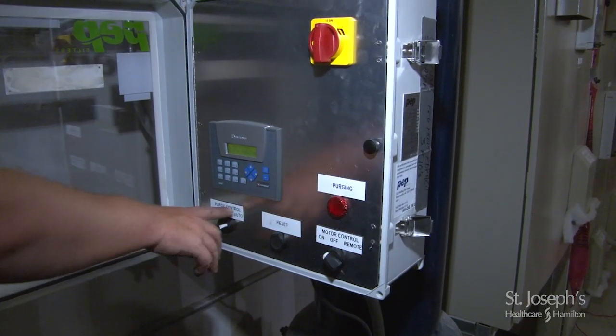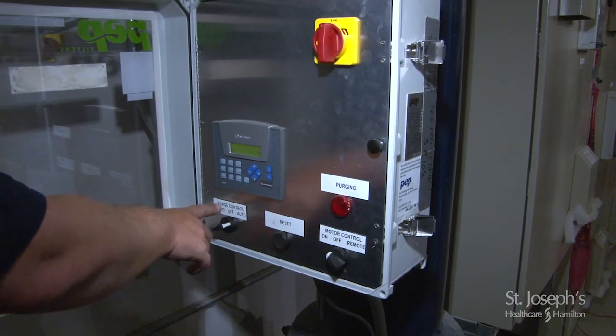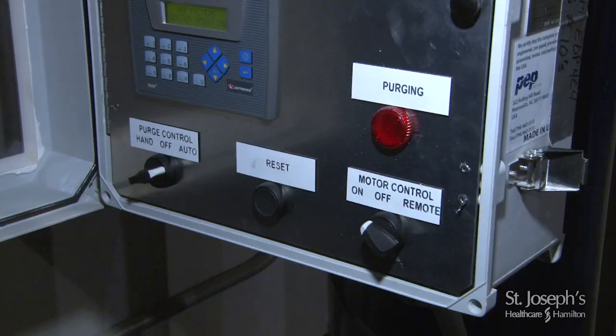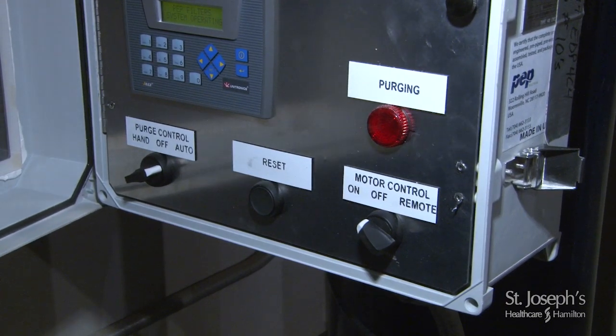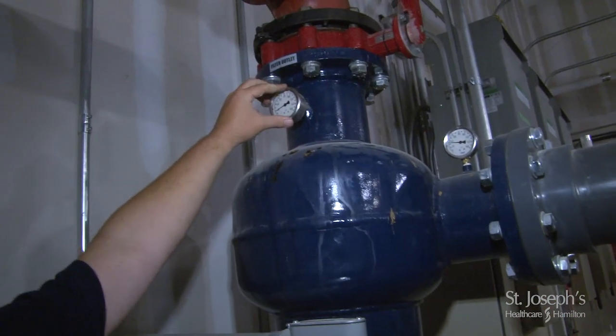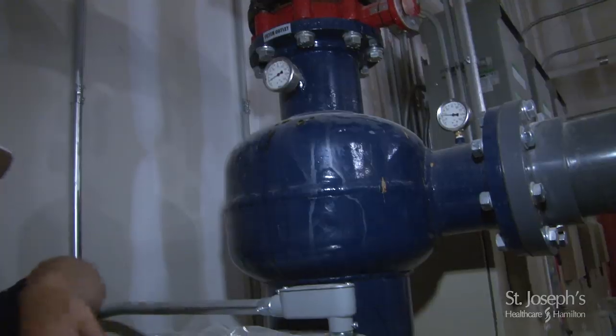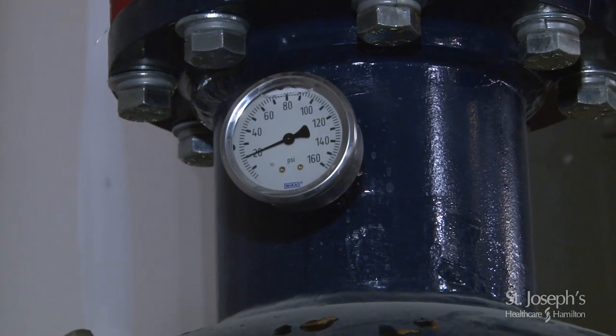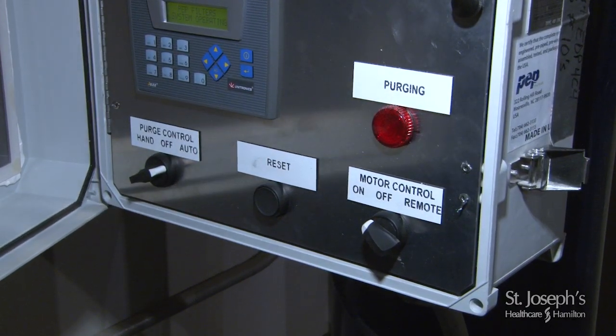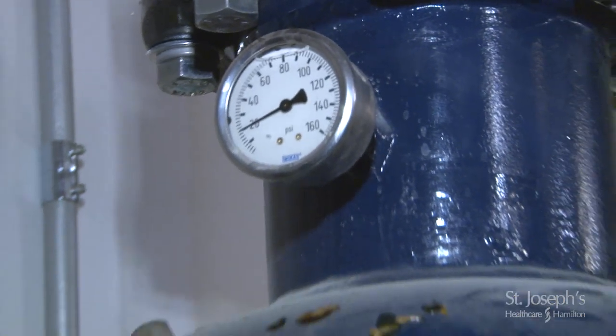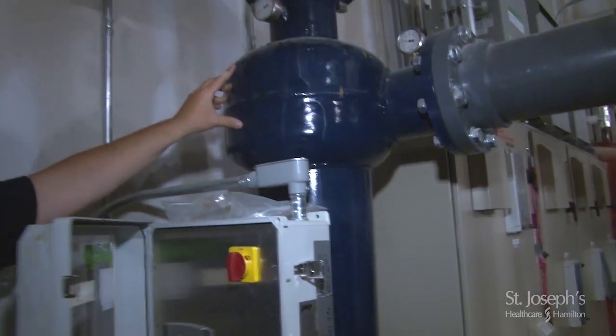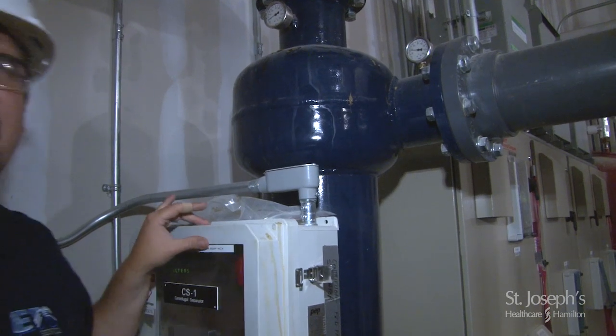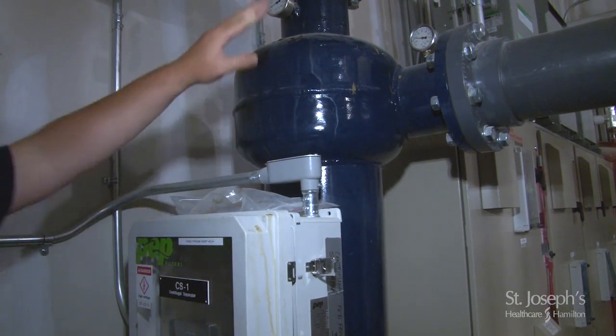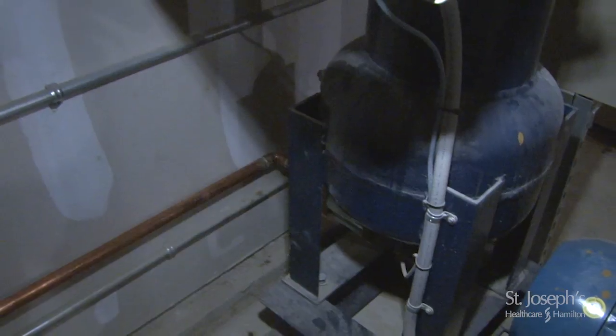Next to it, we have a purge control, always set to auto. What the purge does is a self-cleaning of the unit. How the purge control operates is it's constantly monitoring the pressure coming into the unit and the pressure going out of the unit, and the differential between those two pressures. When that pressure differential reaches approximately 7 to 8 psi, the control board inside is programmed to know that that's a very wide differential in pressure. It assumes at that moment the unit is dirty and needs to be cleaned. It does that itself. It puts itself into purge automatically. It stops the flow of water going back to the tower and sends it out the purge valve at the bottom of this tank. Any sediment on the bottom of this tank will then be purged out through this copper line and sent down the drain.